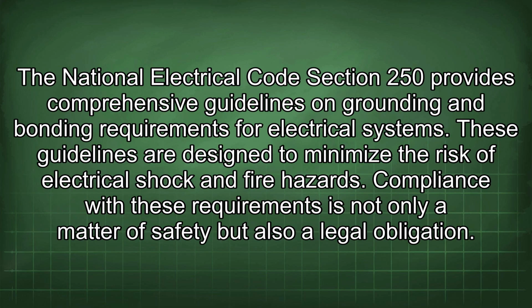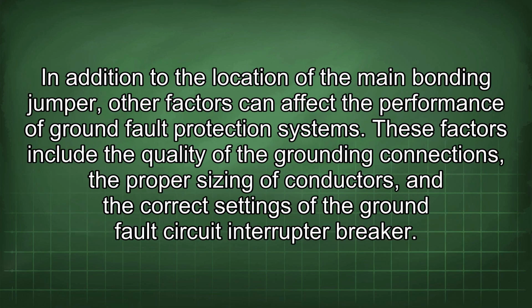The National Electrical Code Section 250 provides comprehensive guidelines on grounding and bonding requirements for electrical systems. These guidelines are designed to minimize the risk of electrical shock and fire hazards. Compliance with these requirements is not only a matter of safety but also a legal obligation. In addition to the location of the main bonding jumper, other factors can affect the performance of ground fault protection systems. These factors include the quality of the grounding connections, the proper sizing of conductors, and the correct settings of the ground fault circuit interrupter breaker.